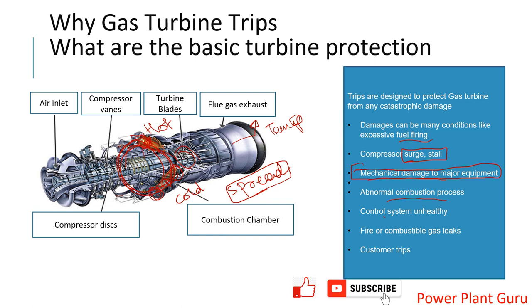Next is control system unhealthiness. A GE gas turbine works on a 125-volt DC control system. If your control system is unhealthy, the brain running the machine is not in a healthy state. In that case we have to shut down the machine to prevent it from any unforeseen situations. That is another kind of protection where we need to be careful.